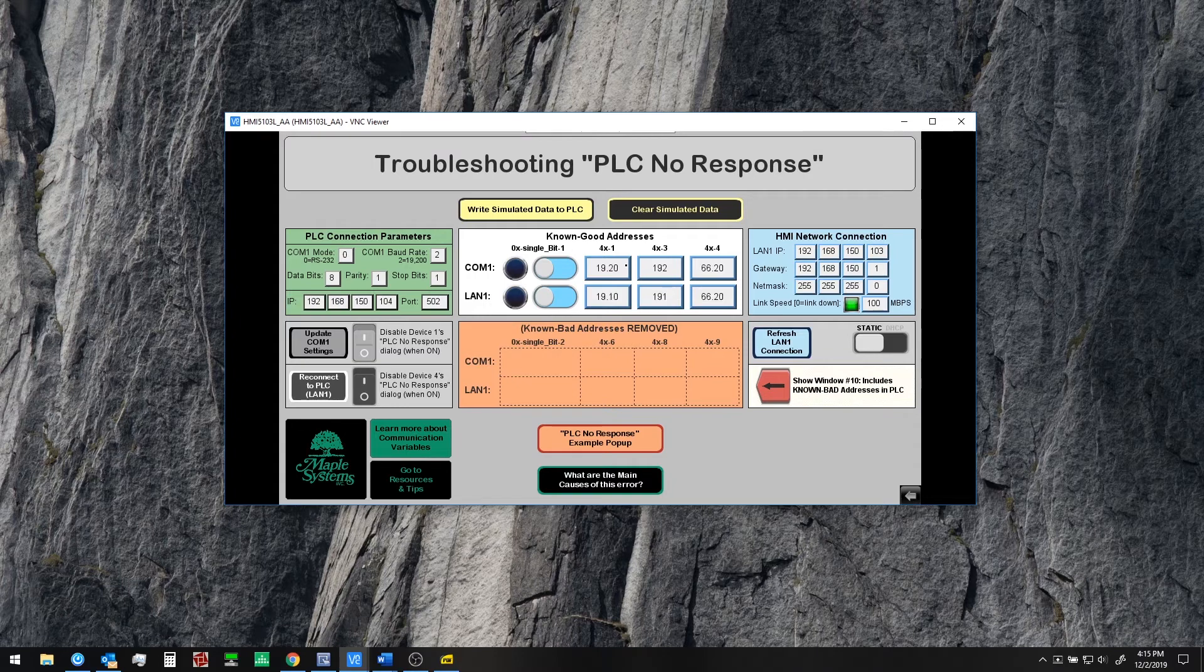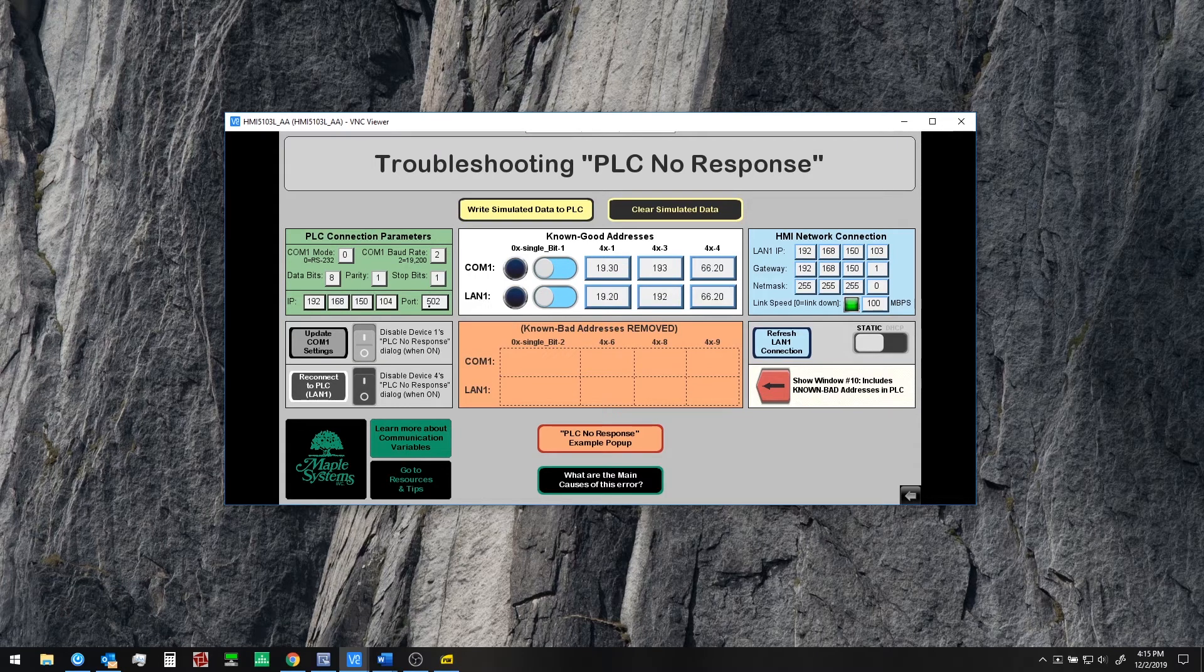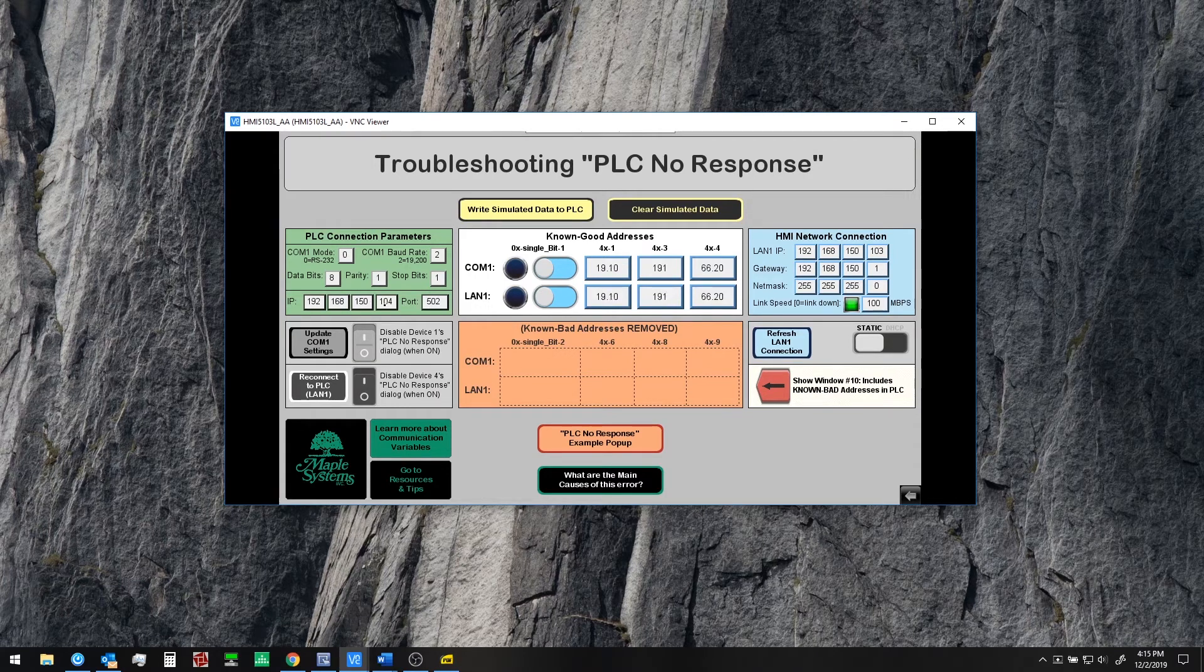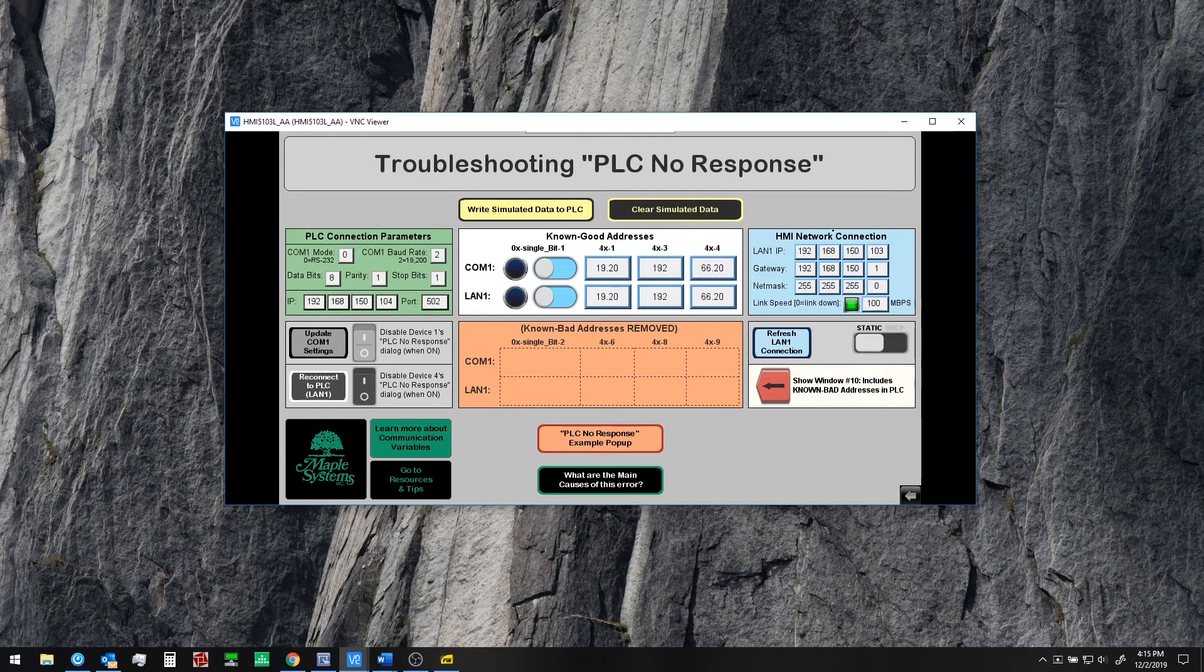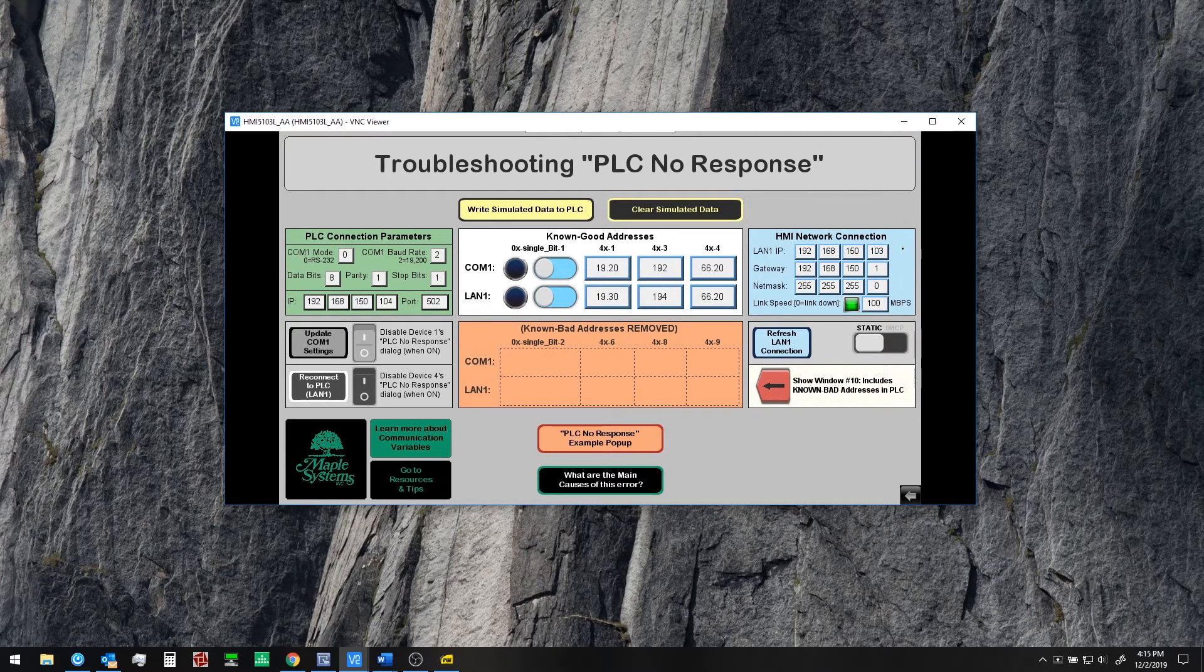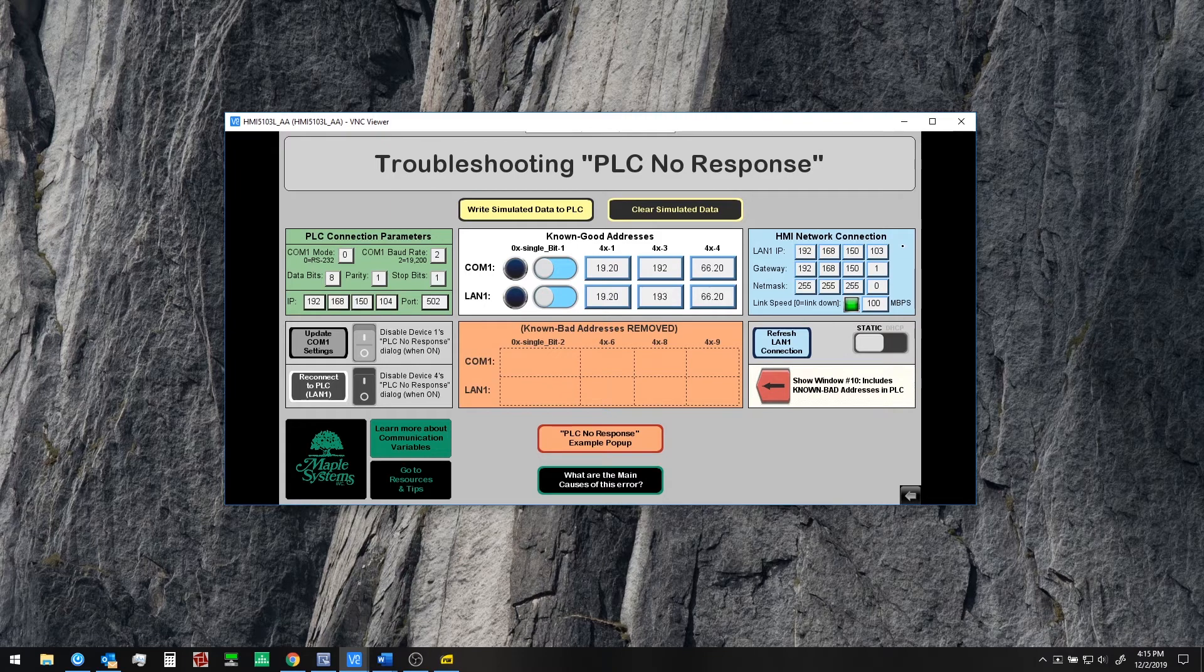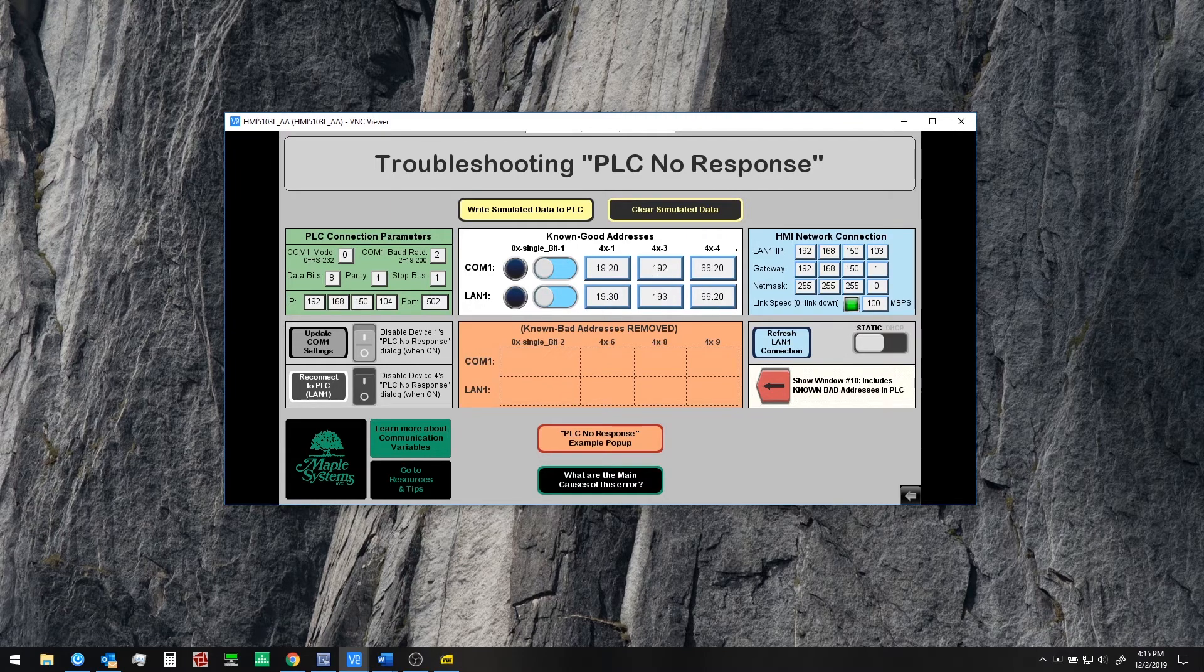So the same thing would apply if you set the wrong port number, wrong IP address for an Ethernet interface. Or if your HMI can't communicate on your network then most likely you'll get a PLC no response message.